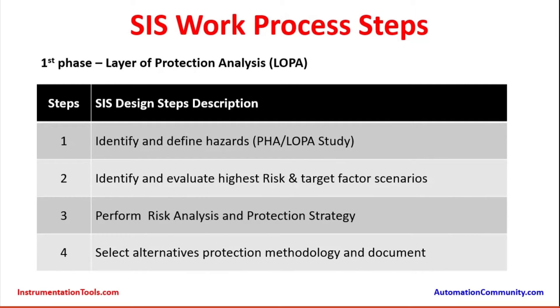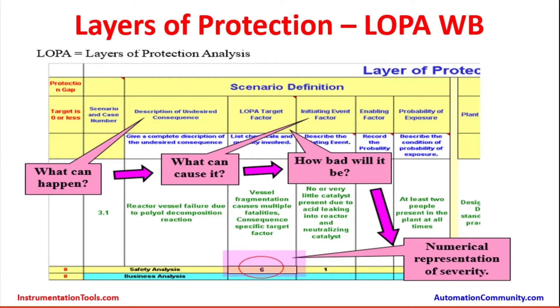The second step is to identify and evaluate the highest risk and target factor scenarios. When the LOPA is being developed, there are many factors to be considered which affect the plant and could lead to a hazard. The LOPA workbook describes the scenario, the undesired consequence — what can happen — and the LOPA target factor. Usually a target factor of 6 is arrived at, though some companies have different standards.